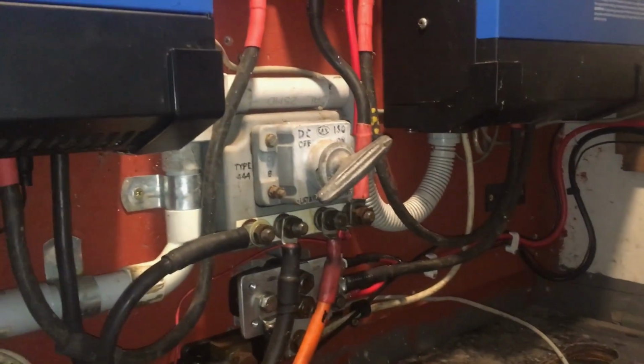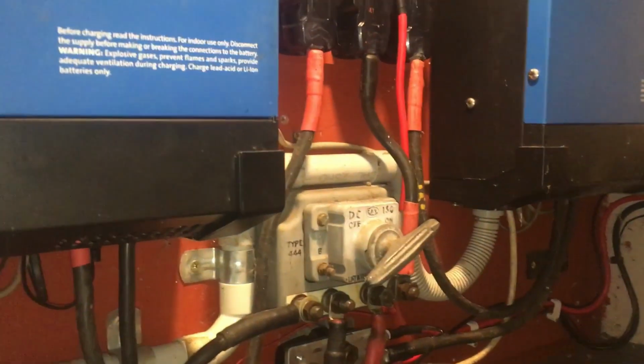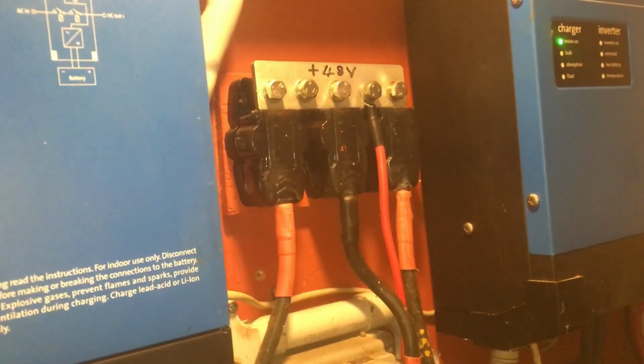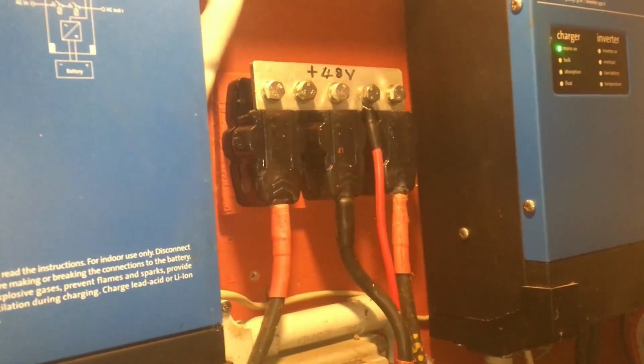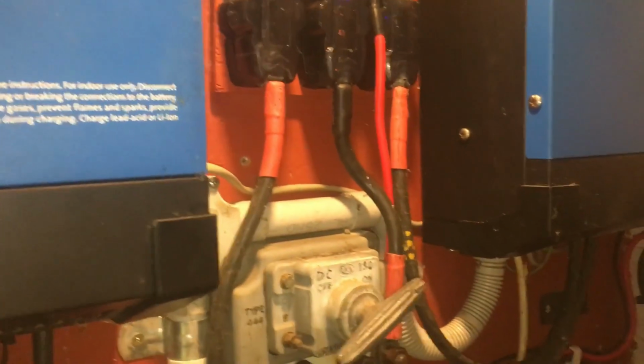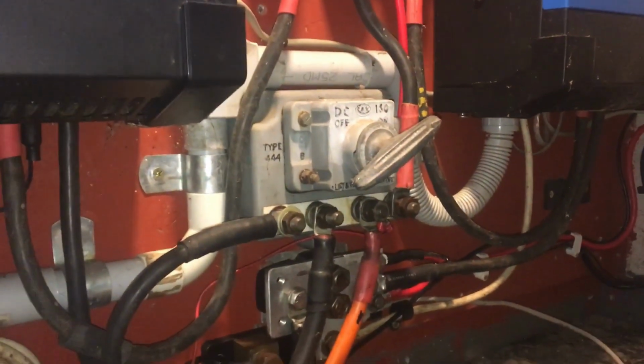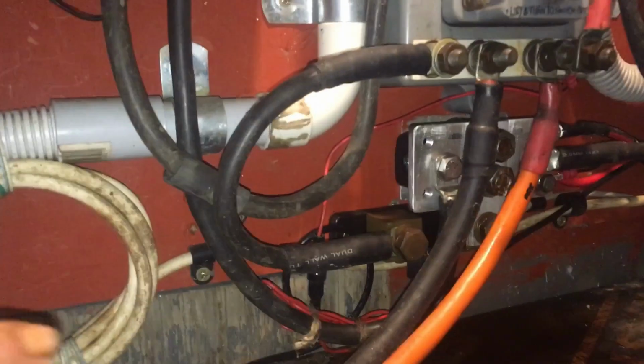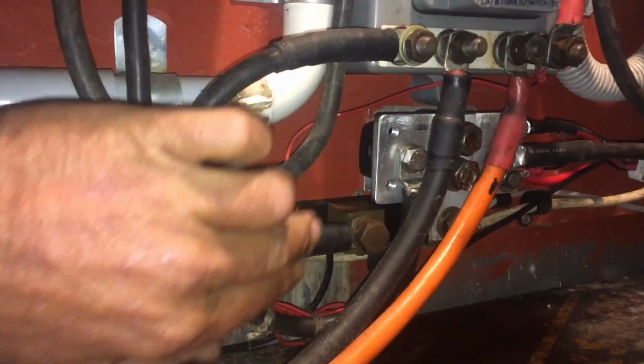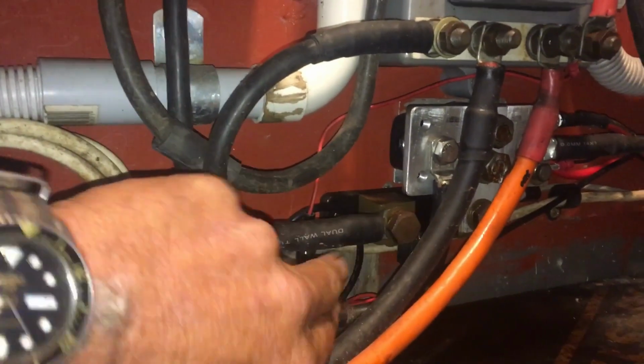So we start at the battery. Main power lines from the battery go to the isolator switch. From the isolator switch, the positive line goes up to the busbar via the main fuse. The two outer fuses are the inverter fuses, one to the master, one to the slave. Okay, the negative line on the left hand side of the isolator goes down to the negative busbar here, and below that is the Victron DC shunt. Can't really see it that well, but there it is. That's the DC shunt there.